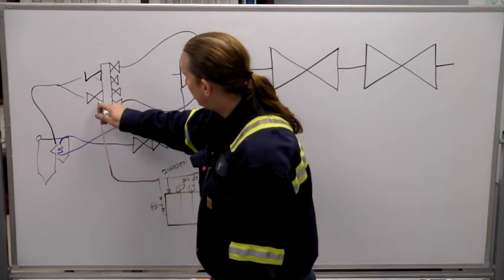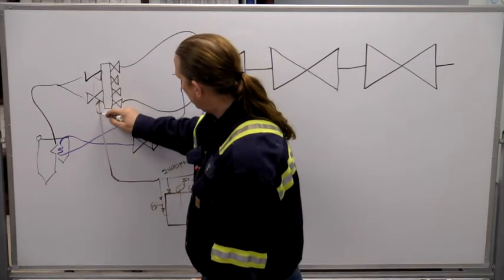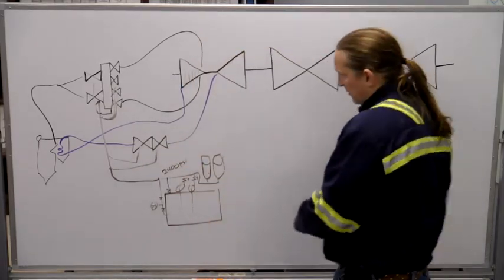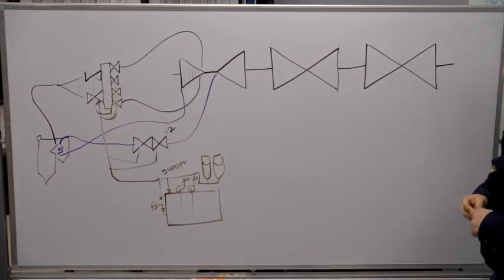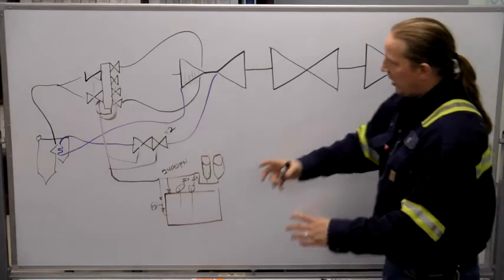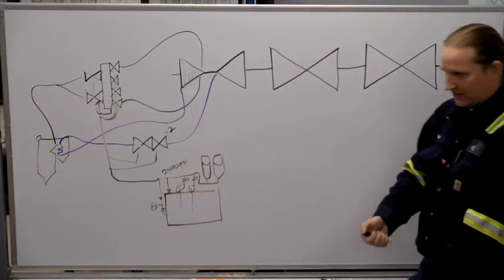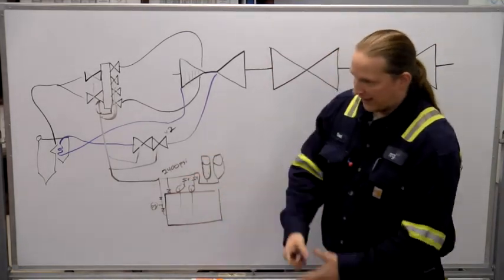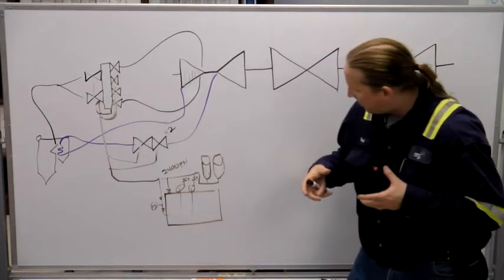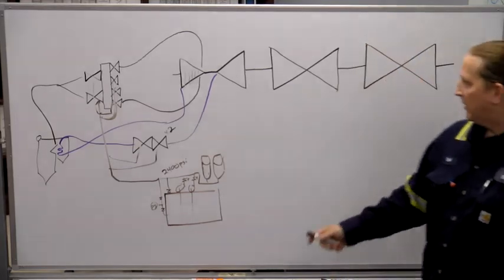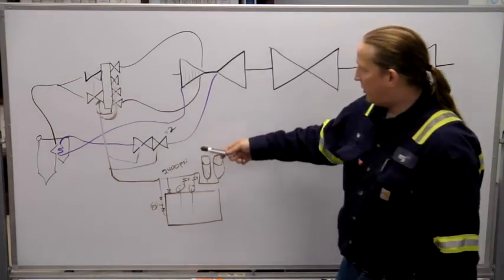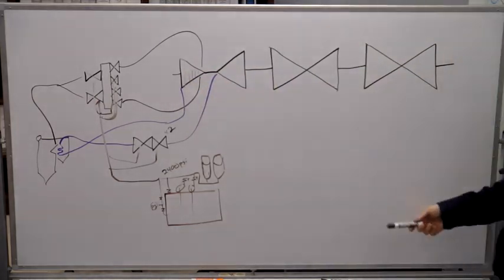The pumps provide oil to the main steam stop valves, the control valves, and the intercept valves. The intercept valve is kind of two valves inside one body — a stop valve and a control valve in a concentric arrangement. If the stop valve is shut, it doesn't matter what the control valve is doing. If the stop valve is open, the control valve can throttle the steam. Practically speaking, these stay open all the time because pinching them back is just a loss of efficiency.